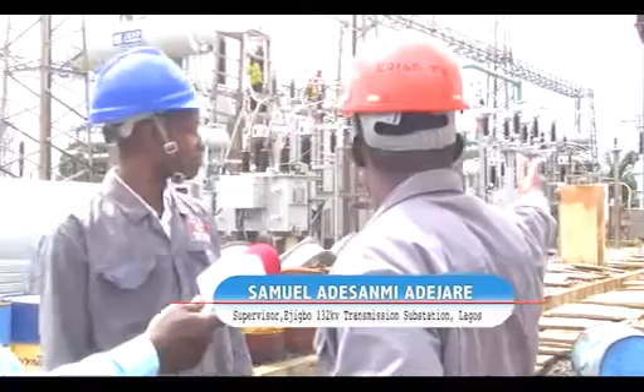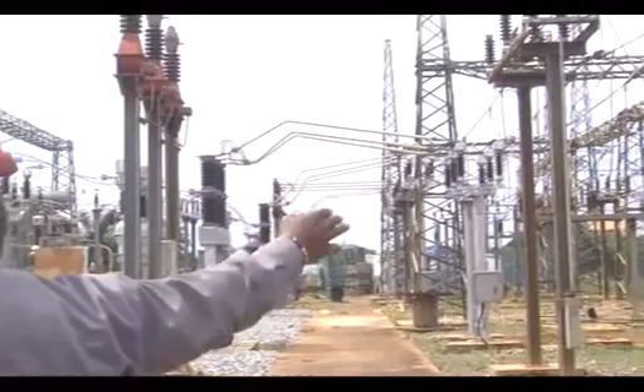They've changed so many pieces of equipment, like our circuit breakers. Something that will withstand 100 MVA will be higher in rating than one that will withstand 30 MVA. If you look at this circuit breaker now, it's a secondary circuit breaker, and likewise the primary circuit breaker, they've changed them. Likewise the isolator, from this side downward is the incomer, this is the outgoing. They've changed everything, like our GT giving us station supply, they've replaced it, and likewise that one. So all these, CT, isolators, breakers, up to this level, they've changed everything in order to conform with the present capacity.